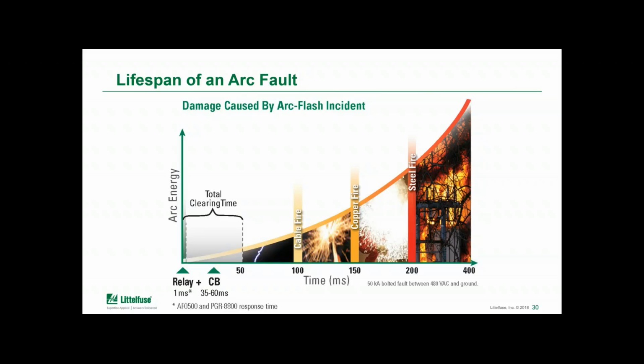So if we want to shift from current limiting fuses and talk about another product that can be designed in to retrofit existing equipment, that product is an arc flash relay. The principal idea of an arc flash relay is to limit the time that an arc persists in the event of a fault, and therefore it minimizes the energy released. With detection and response time that's less than a millisecond, the limiting factor in that equation would be the interrupting device that's being used, and of course how well it's maintained.